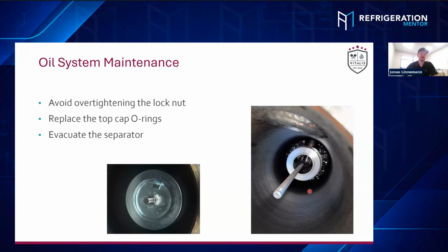And another thing is, whenever you open anything in CO2 systems with an O-ring, make sure you have a spare one with you. Because the high CO2 pressure is sometimes absorbed by this rubber material, and as soon as you open it, it starts to blow up. It looks like blowing up a balloon. These O-rings expand a lot and get very thick. Sometimes they break. Sometimes it takes hours for them to shrink back in position. So typically you can't reuse them. So make sure before you open it that you get the right O-rings on hand.